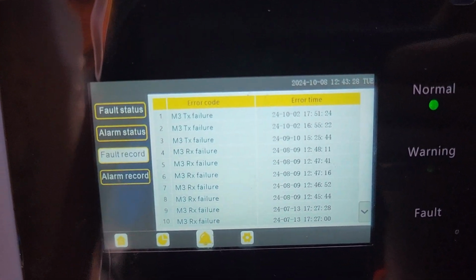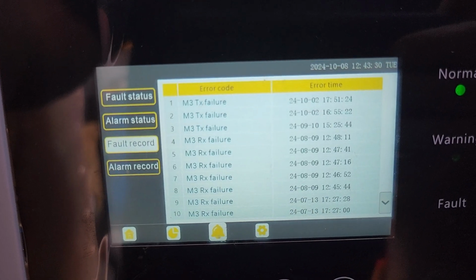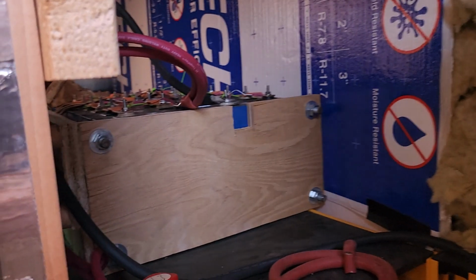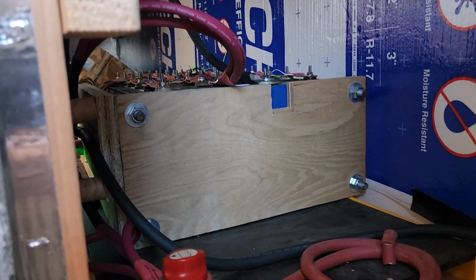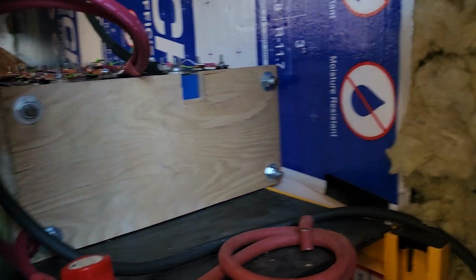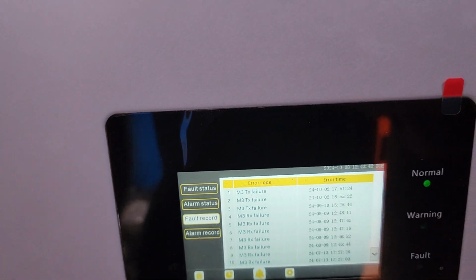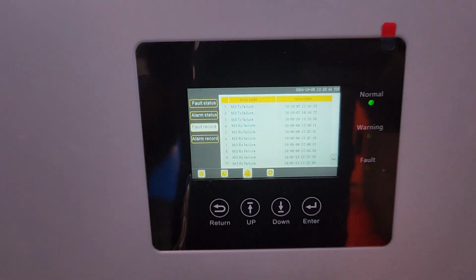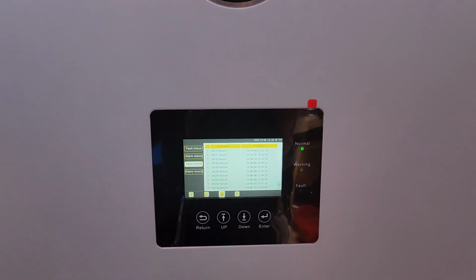My thinking is that the inverter is set to 280 amp hours, and the Seplos BMS is set to 200. So when the Seplos BMS reaches 200, it shuts off the charging, causing a fault in the inverter because the inverter is trying to push 280 amp hours. So we get a fault code.